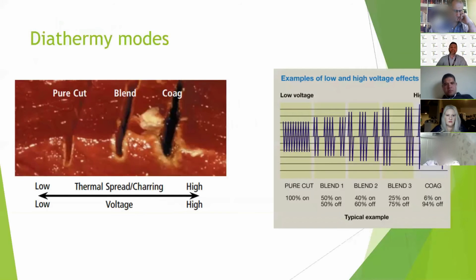And just to describe it, if you look here, on the left-hand side is pure cut, on the right-hand side is coagulation, and the middle is a blend. And if you go further on the right, you will have the fulguration, which is even bigger damage around the area. And these are the frequencies or the voltages of how they look between coagulation and cutting. You can notice that if you look at my arrow, for the coagulation, there is one wave and then a pause and then another wave, while in the cutting, it's continuous.